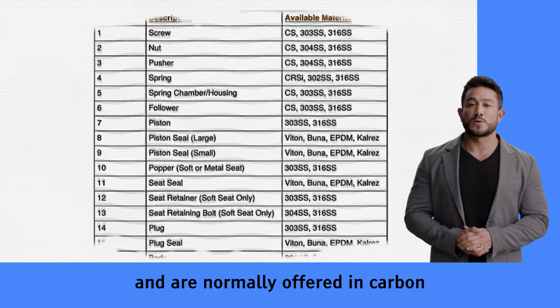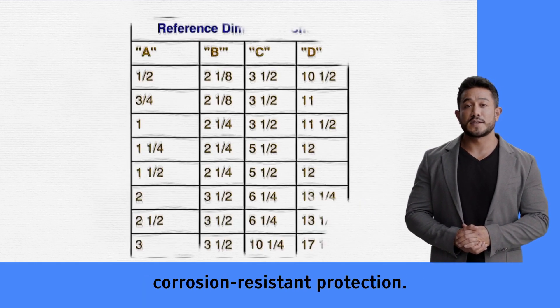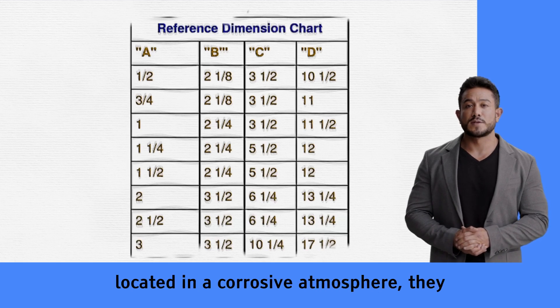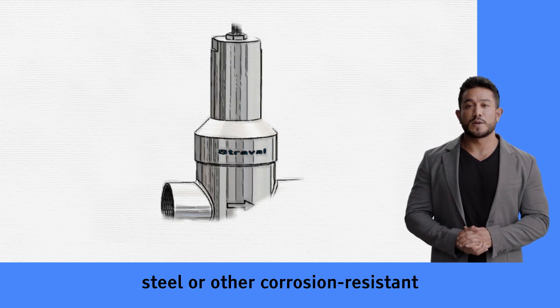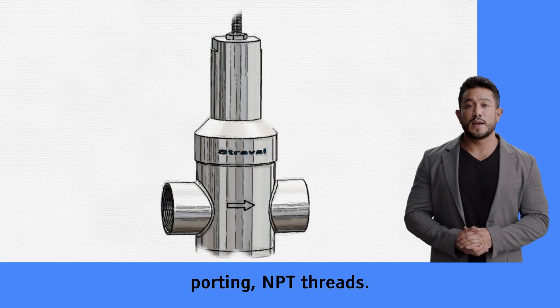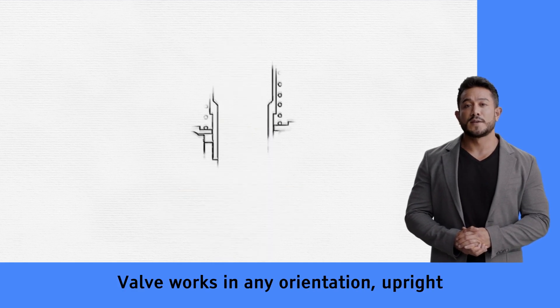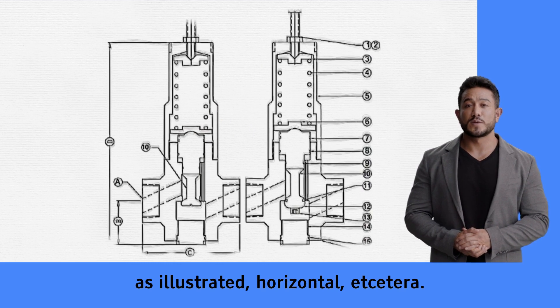The spring chamber and adjusting spring parts are non-wetted — not in contact with the fluid or gas — and are normally offered in carbon steel painted for minimal exterior corrosion protection. When these parts are submerged or located in a corrosive atmosphere, they can be upgraded to stainless steel or other corrosion-resistant materials at an additional cost. Standard porting and line porting with NPT threads are available. The valve works in any orientation: upright as illustrated, horizontal, etc.